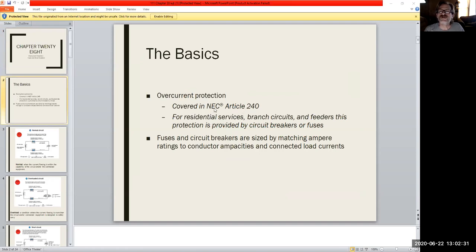If you looked up NEC Article 240, it pretty much states that for residential services, branch circuits and feeders, this protection is provided by circuit breakers or fuses. Meaning that if any given line were to experience an extreme current draw of some sort, something on that line supplying that voltage is going to disengage and keep the power from feeding it. And this is for fire prevention and other dangers that could be happening.